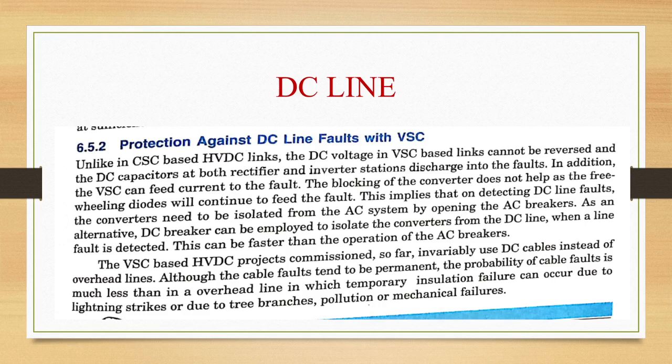Protection against DC line faults with VSC. Unlike in CSC based HVDC links, DC voltage in VSC based links cannot be reversed, and DC capacitors at both rectifier and inverter stations will discharge into the fault. In addition, VSC can feed current to the fault. Blocking of the converter does not help, as the freewheeling diodes will continue to feed the fault.